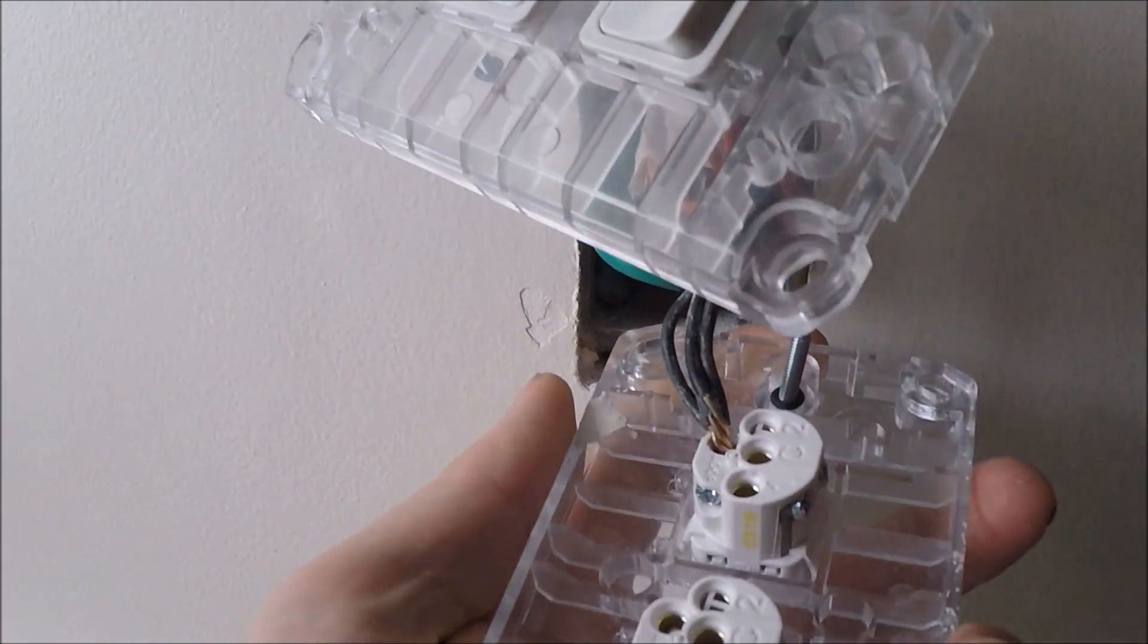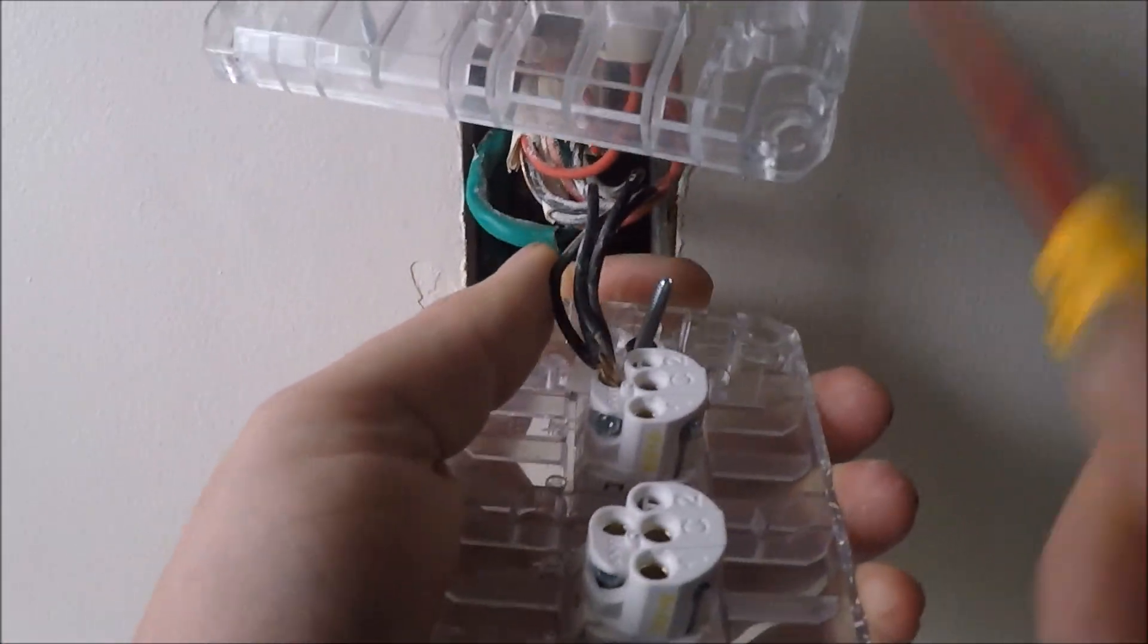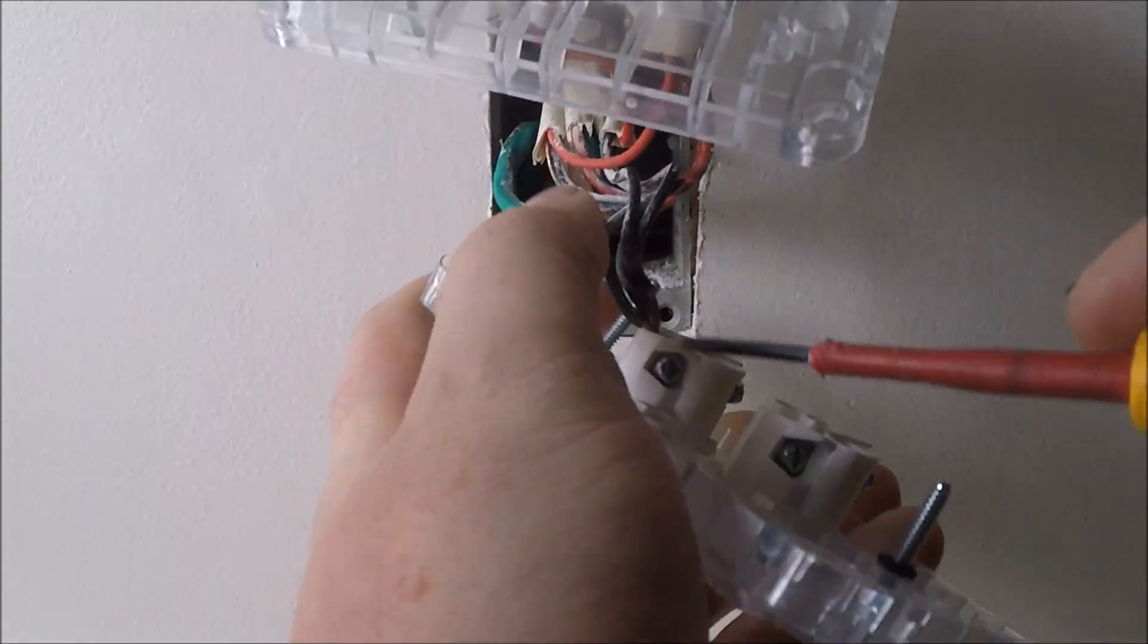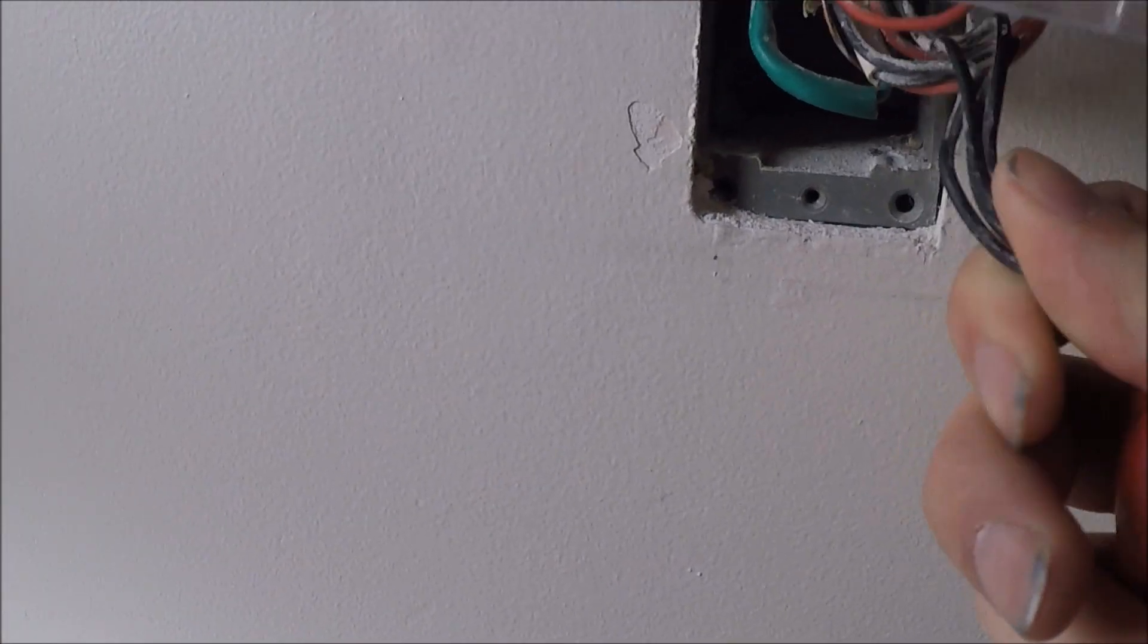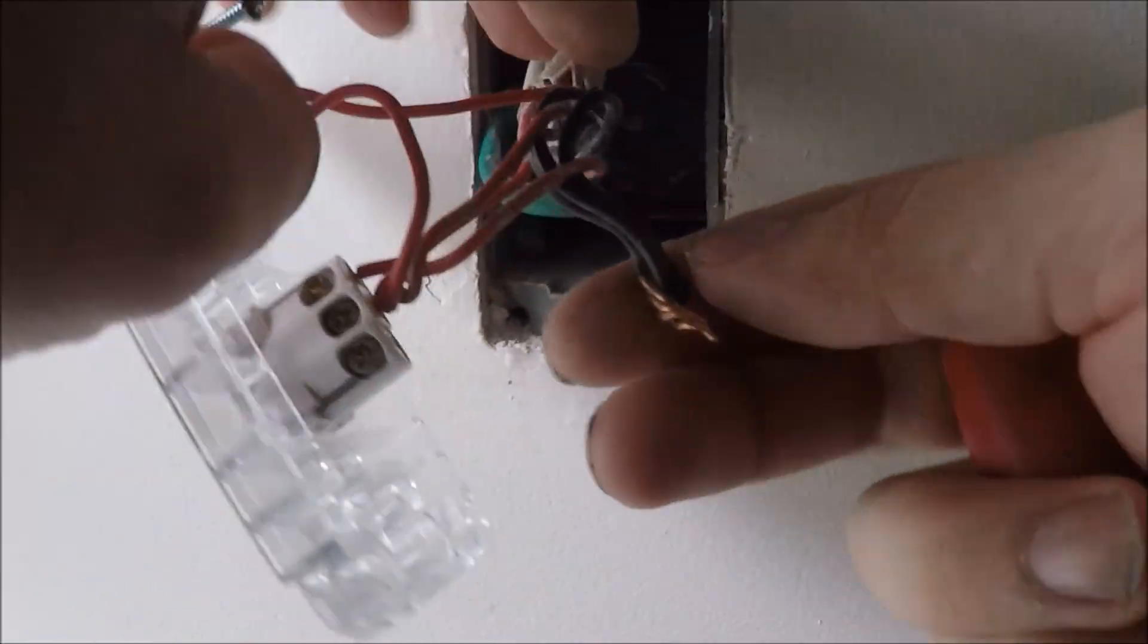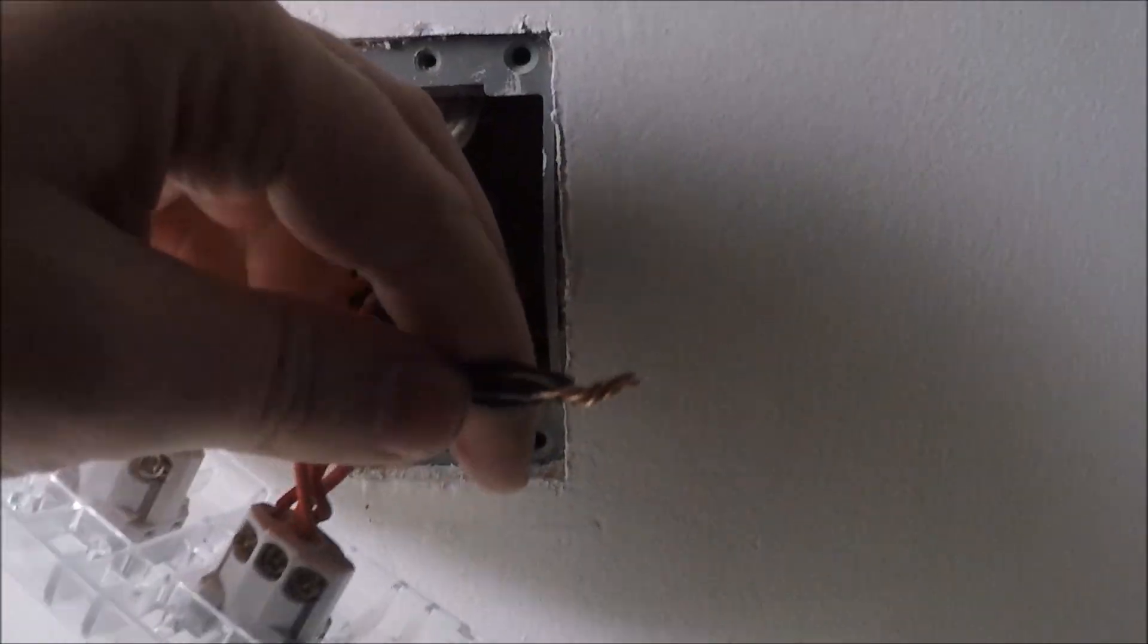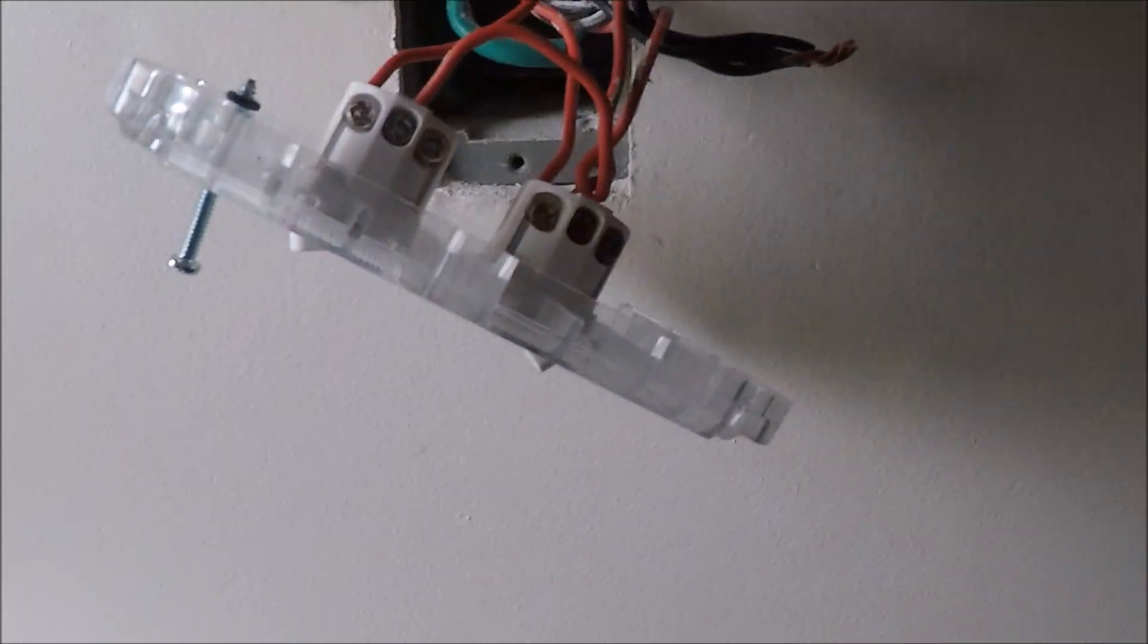There's no earths at these switches because they were installed before it was illegal to not install earths. So these neutrals obviously need re-terminating. See the twist has come undone and they've been rushed by the looks of things.